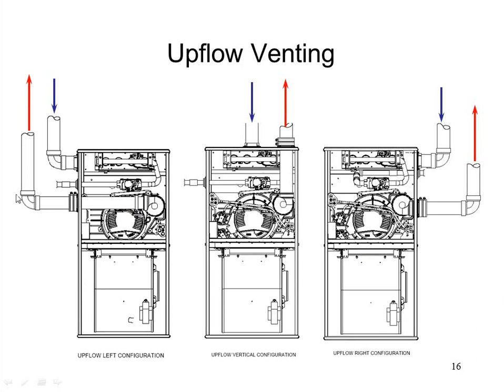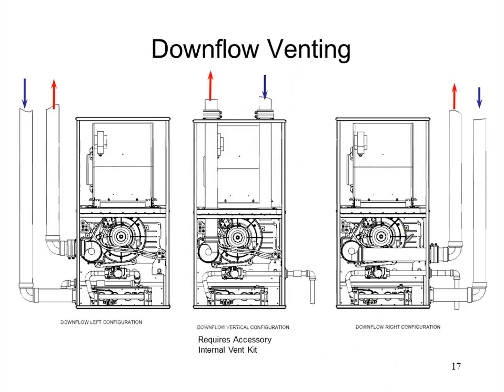Like I said, on the venting, we can go out the left side, the right side, or out the top. You got your choice on that. This is an upflow configuration for the furnace, meaning that air is moving up through the furnace this way, right? So I can bring my combustion air and exhaust from the top, left, or right. If I go to the downflow configuration, that means I flip my furnace a full 180 degrees, right? And now my airflow is moving in this direction. So that means my combustion air can be the left, the right, or obviously I can't go at the top anymore because the top is now down and I don't want combustion going down.